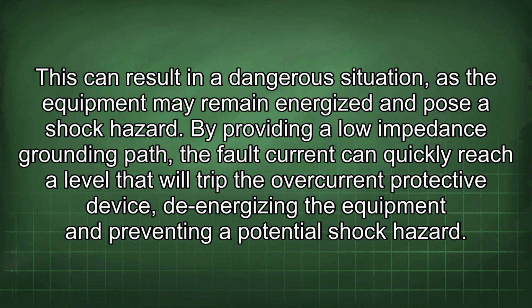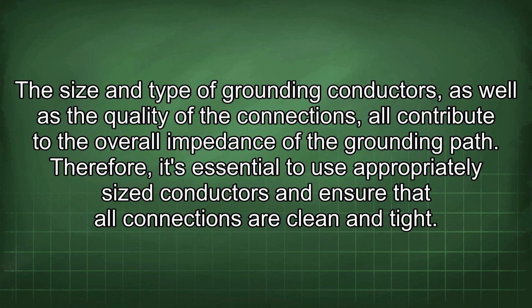This can result in a dangerous situation, as the equipment may remain energized and pose a shock hazard. By providing a low impedance grounding path, the fault current can quickly reach a level that will trip the overcurrent protective device, de-energizing the equipment and preventing a potential shock hazard. The size and type of grounding conductors, as well as the quality of the connections, all contribute to the overall impedance of the grounding path. Therefore, it's essential to use appropriately sized conductors and ensure that all connections are clean and tight.